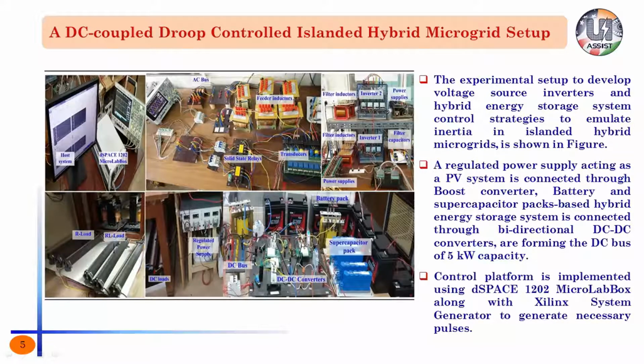These are made up of IGBT stacks, and the DC bus, common to both inverters made up of Semikron inverter stacks, is connected in common. The inverters form the local bus or point of common coupling AC bus through a proper LCL filter, with feeders considered using proper resistance and inductance values for the system, and these are the filter sections used.